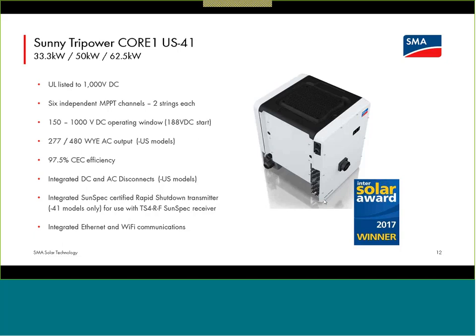So you may not need all of that flexibility, but as part of a retrofit effort, if the array is being investigated and there are modules that are underperforming, damaged, whatever, you have the flexibility to perhaps remove a few modules and end up with different string lengths. If you are putting the CORE1 where that combiner box might have been, where you expected many equal length strings to come in, you now have the flexibility of having potentially different string lengths come to the different input channels for the CORE1. So as the inverter hardware is being modified, the array can be investigated, and if modules need to be quote-unquote orphaned, you may leave them in place for visual appearance, but just disconnect them electrically. The CORE1 can handle that very easily.